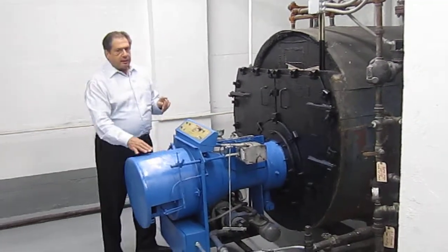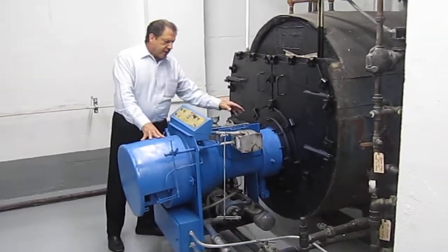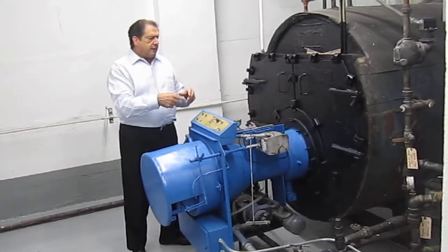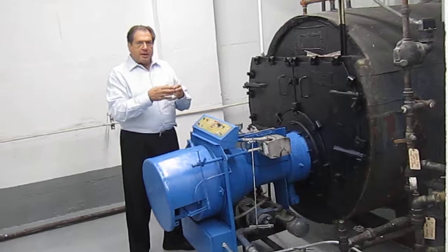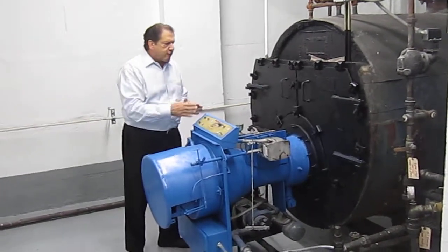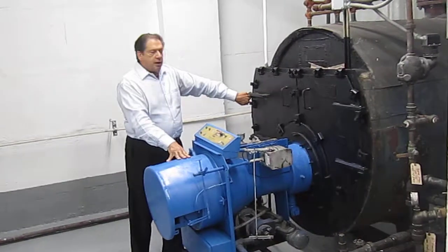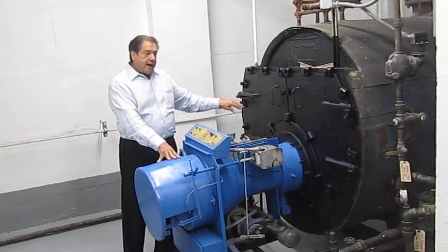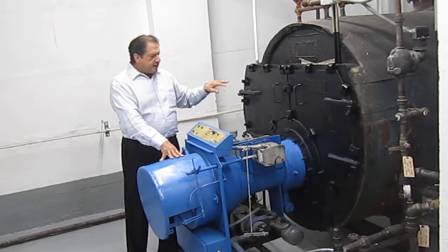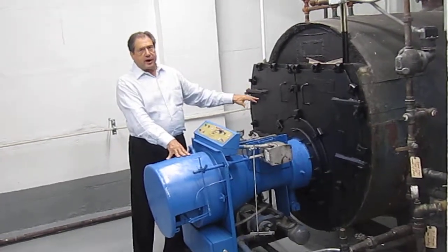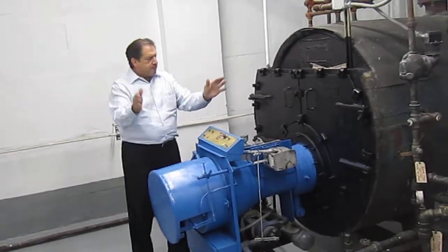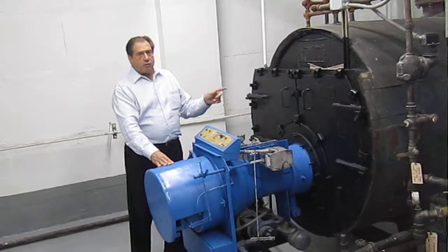The other thing that I didn't talk about before is that when we spoke about the cup and maintaining the carbon on the cup, if that cup isn't properly maintained and carbon does build on one side or the other, when the cup is spinning, the flame will go to one side or the other in the fire chamber. And when that happens, it starts to affect the brick or the chamber itself, and it damages the brick inside the fire chamber. So it's very important that the flame burns in a cone-type shape constantly with that rotary cup operating.